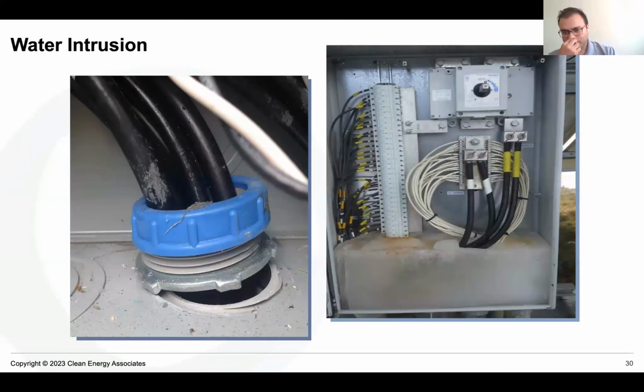A few more points to add. When we go to a site, we always recommend the conduits be filled up and sealed off with an appropriate, listed sealant. The question we always get is, show me the code, show me the NEC code. My response is, yes, unless the conduits are coming from a different temperature area to another, for which there is a code, a lot of times we recommend this as a best practice. No seal is a perfect seal, and it doesn't take a lot of time or money to seal the conduits. It's a simple job that can be done before commissioning the site.